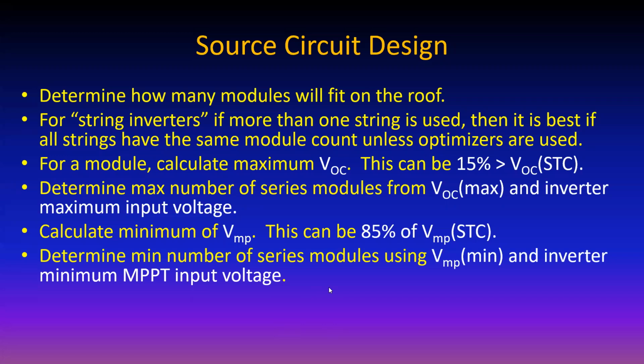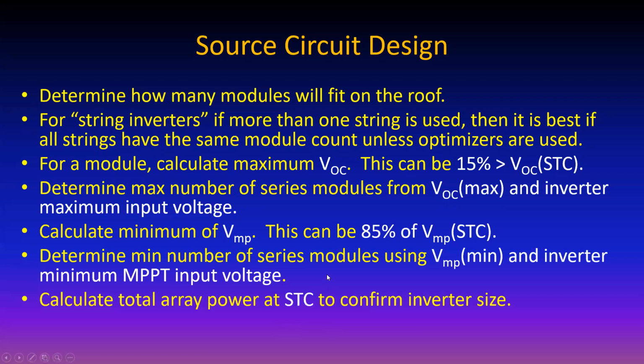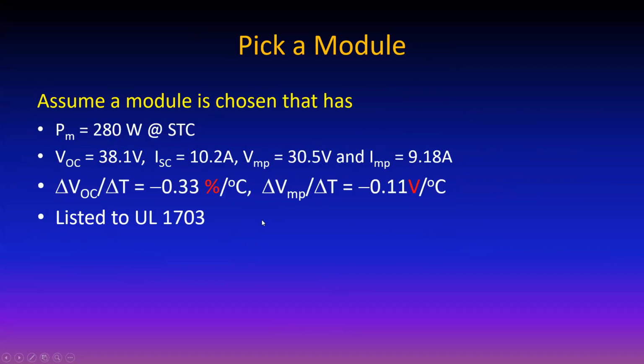Okay, let's actually do this. Then we calculate the total array power at standard test conditions to confirm the inverter size, because once you know the array size, we then need to find an appropriate inverter to go along with the array. So take a module. Here's one that we had before, and notice here it shows the temperature dependence. It gives open circuit voltage, short circuit current, maximum power voltage, which is at about 80% of the open circuit voltage, and maximum power current, which is about 90% of the short circuit current. That's pretty close, but the algorithms that they use in the maximum power point trackers do a whole lot better job than that.